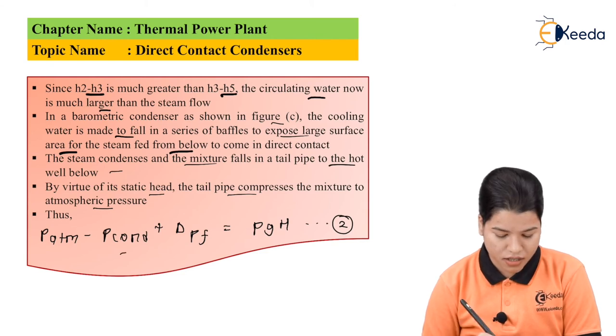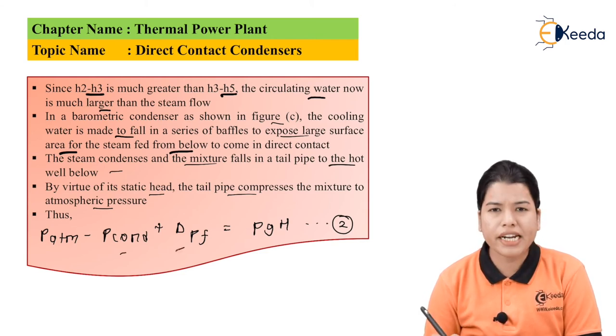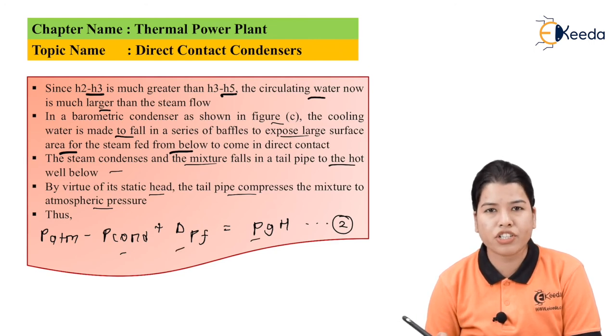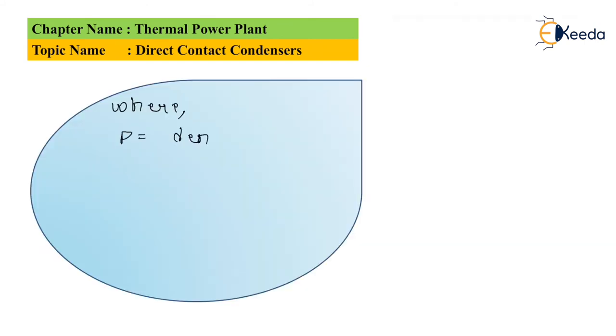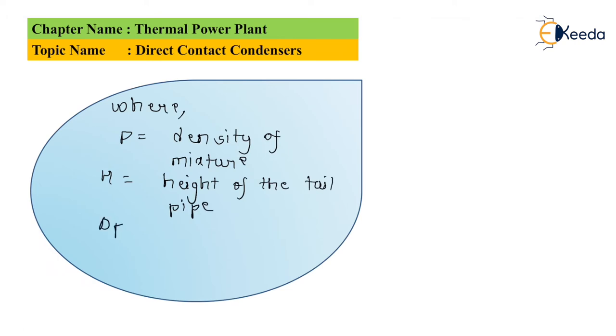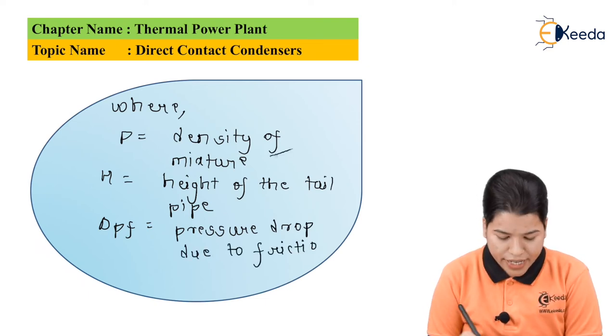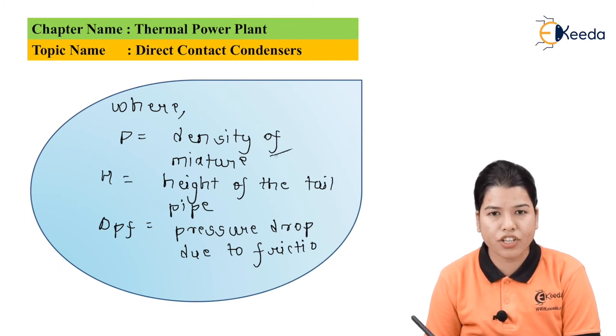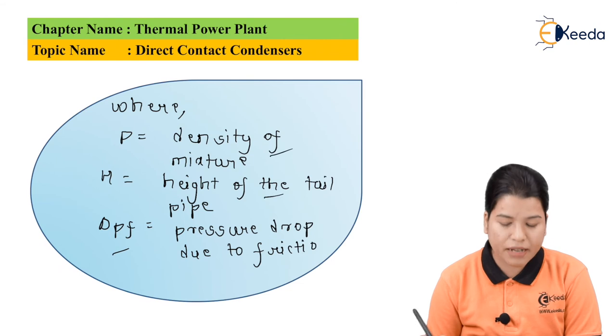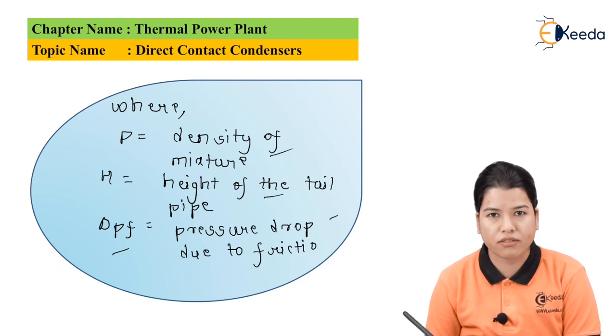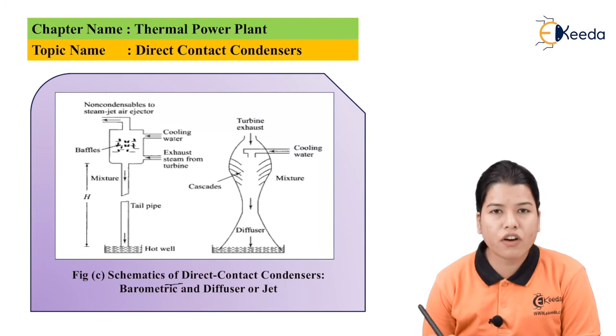Therefore, P_atmosphere minus P_condensate plus delta_pf equals ρgh — this is equation number two. Where ρ is the density of the mixture, h is the height of the tail pipe, and delta_pf is the pressure drop due to friction. Figure C shows the schematics of direct contact condensers — barometric and diffuser (jet).